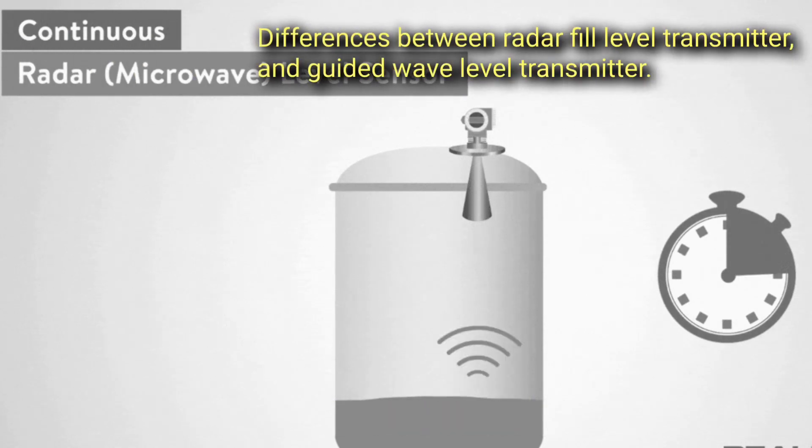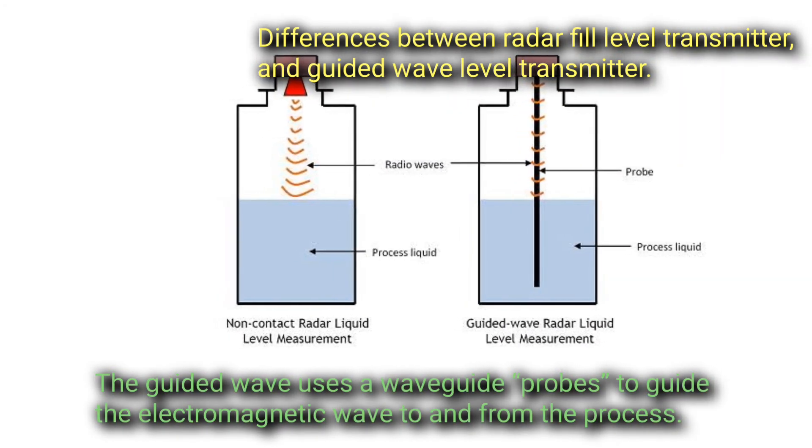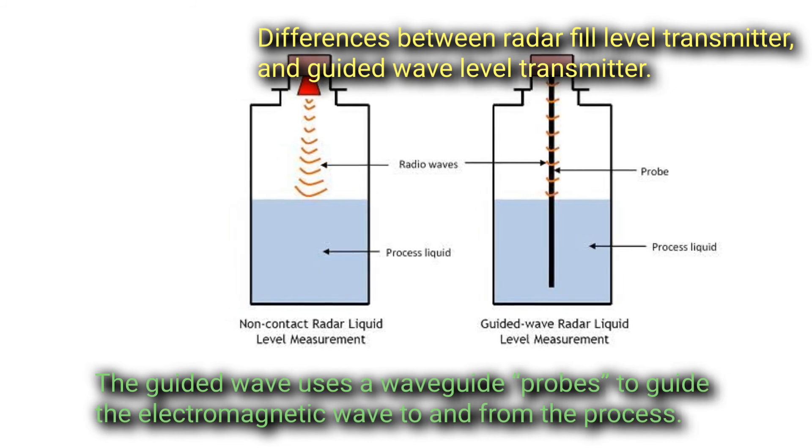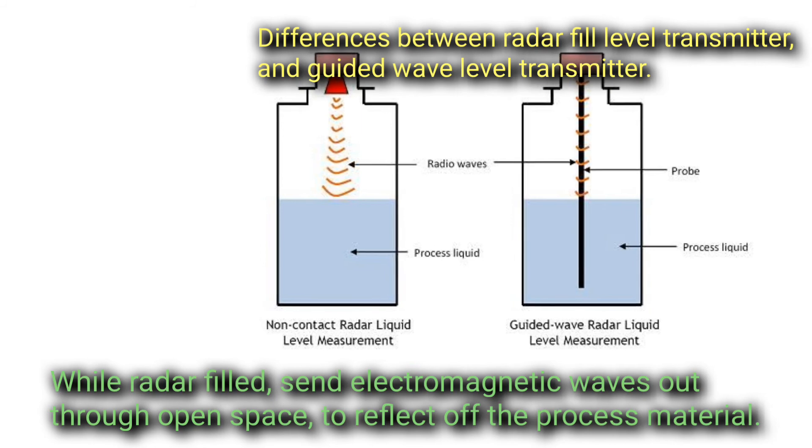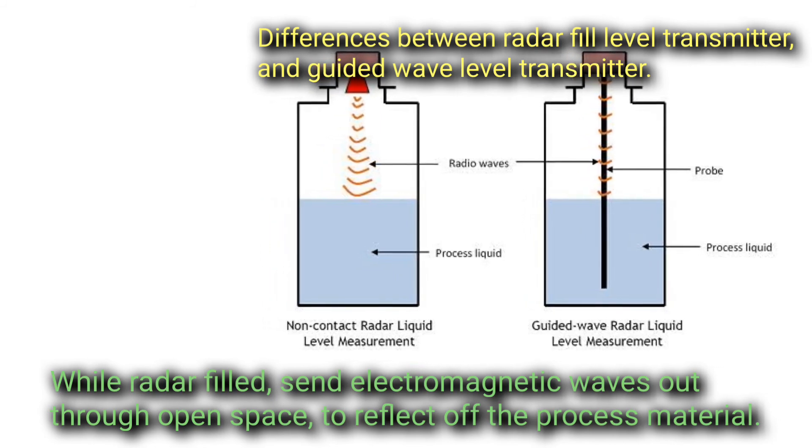Difference between radar fill level transmitter and guided microwave level fill transmitter is that the guided wave uses waveguide probes to guide the electromagnetic wave to and from the process, while radar fill sends electromagnetic waves out through open space to reflect off the process material.